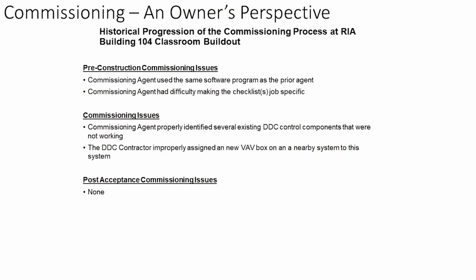Again, he used the same software that the other commissioning agent used, and he had a hard time modifying that to be job specific. Software was always driving it to be job generic. And here I say he identified several existing DDC control components that were not working. So we fixed those. The only problem we had was the DDC contractor improperly assigned a new VAV box to a nearby system. Nobody caught that until I looked at how his programming was set up. This VAV box was on a completely different system, yet it was tied into the decision making on this other system. No post-commissioning issues that I'm aware of.